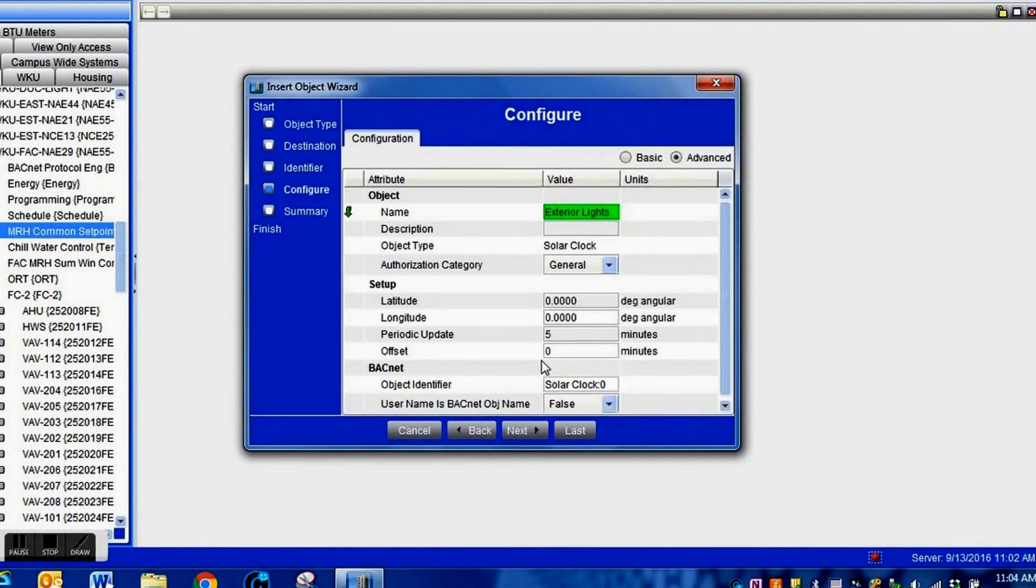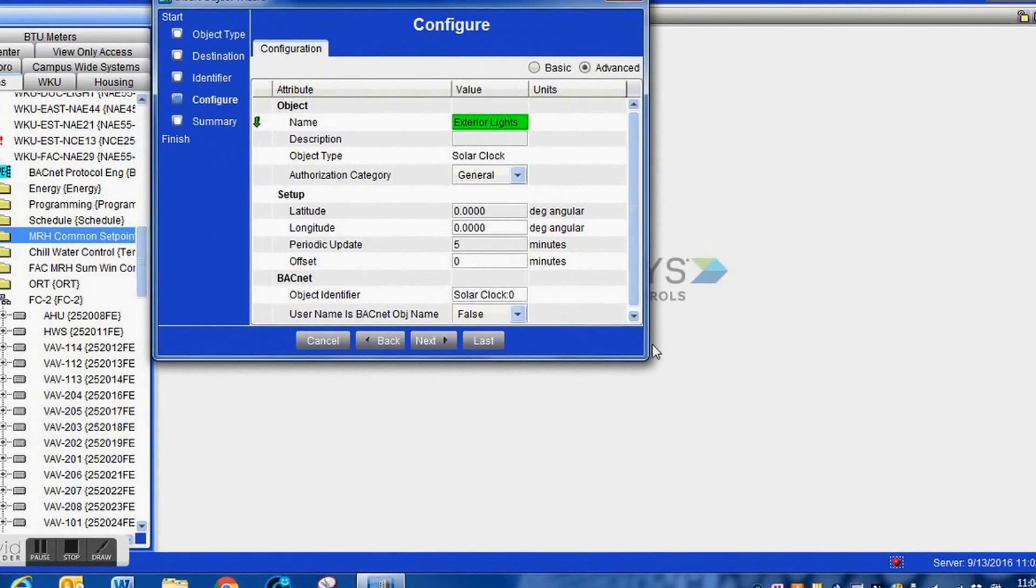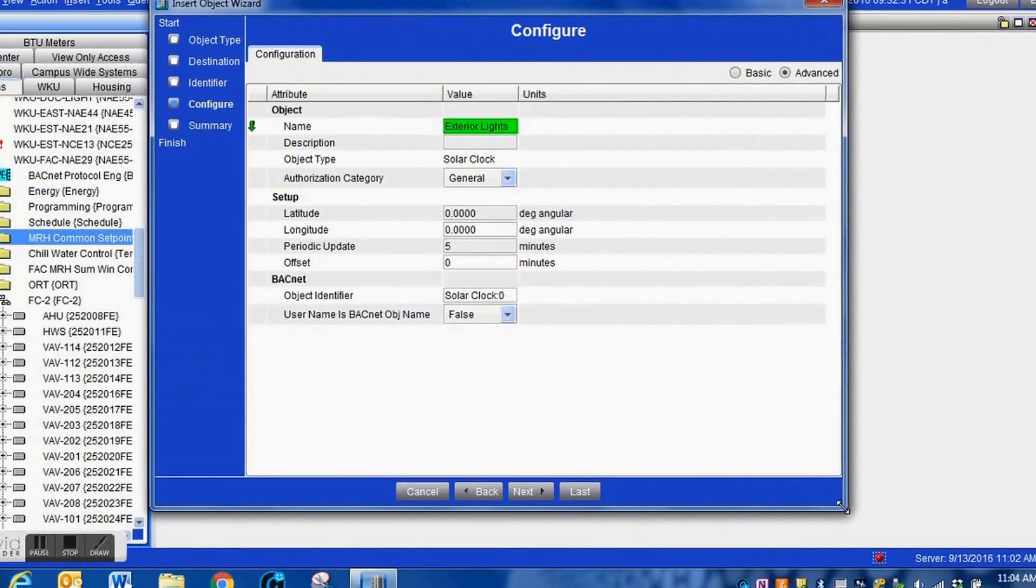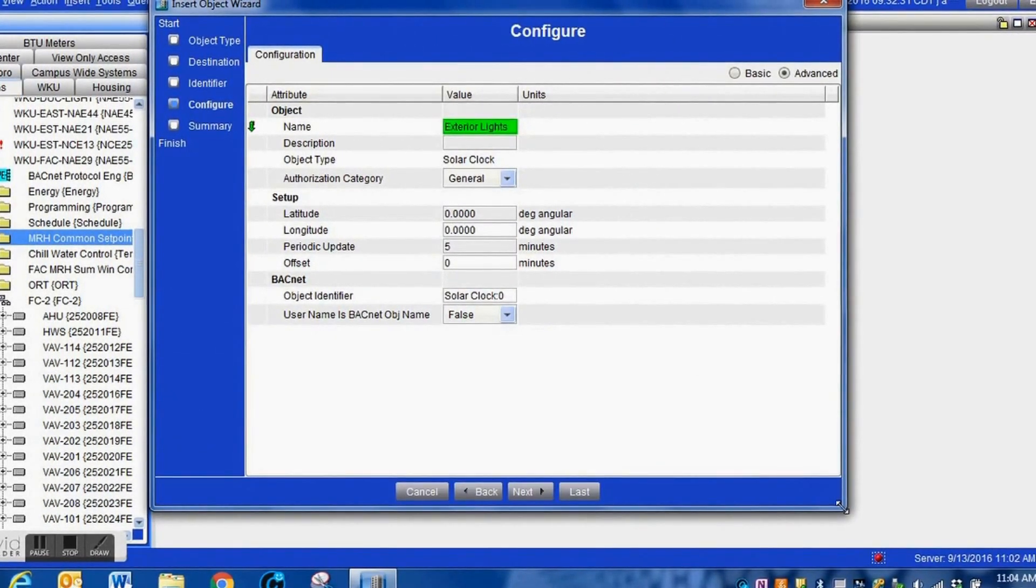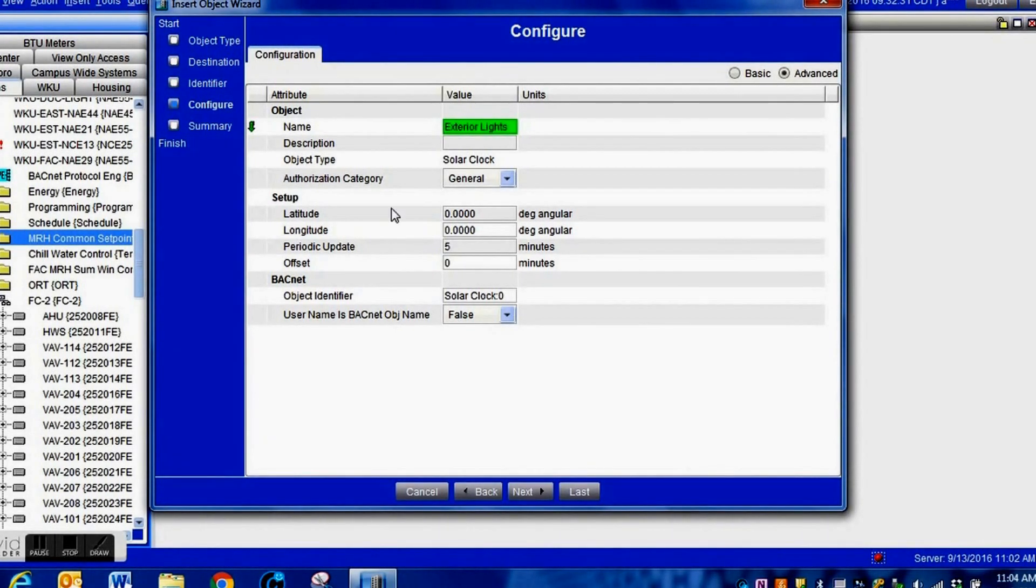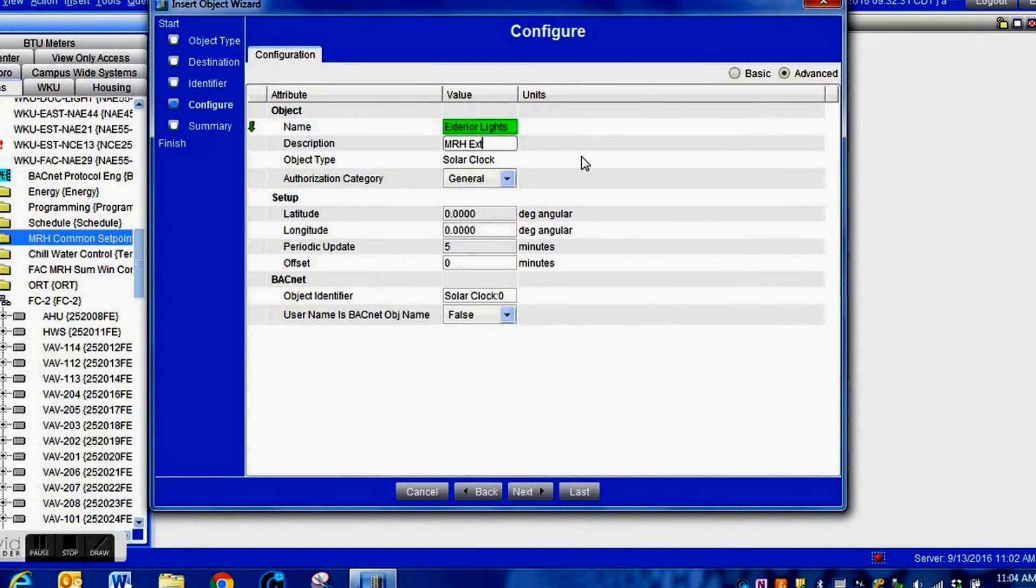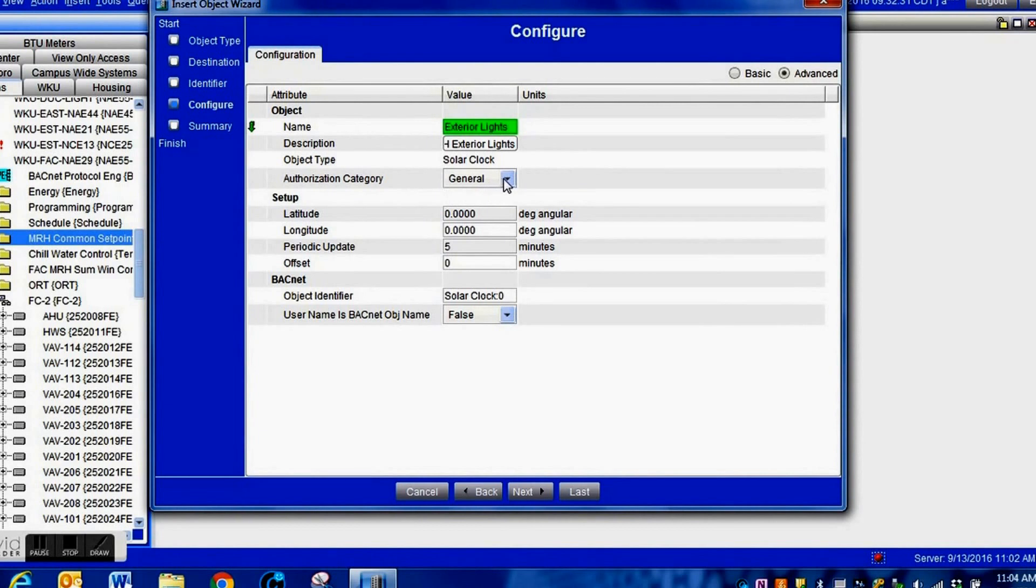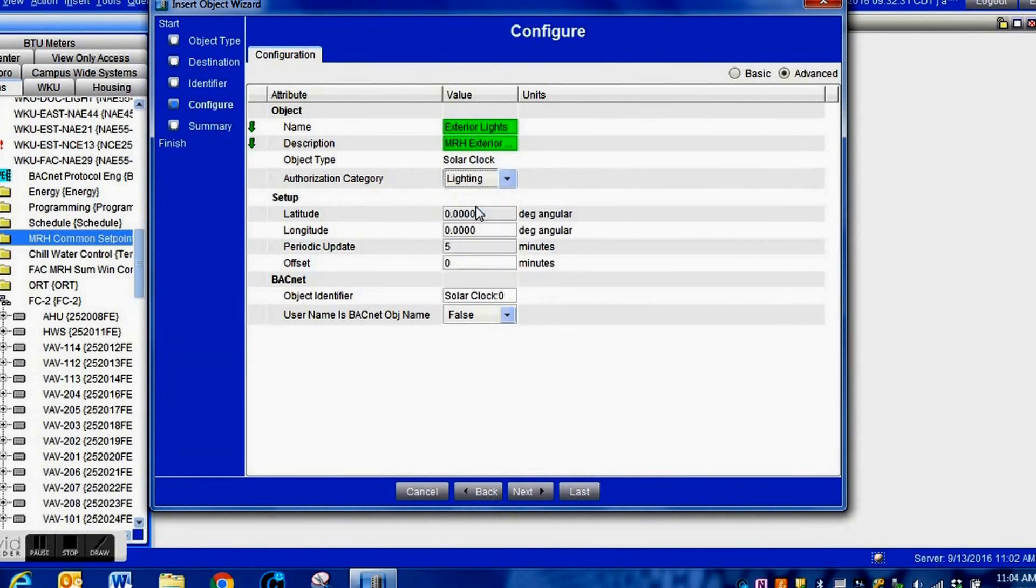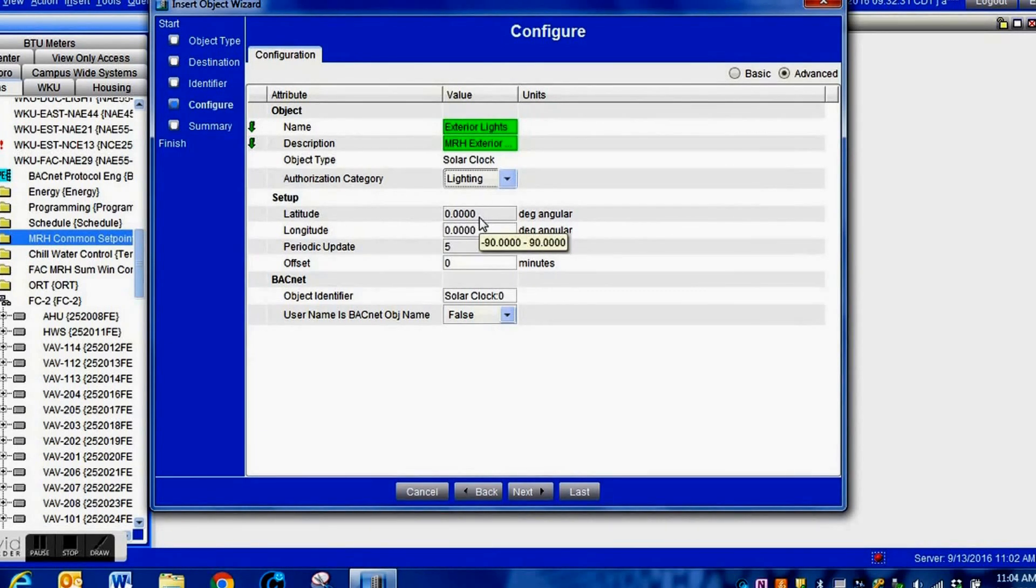This is the configure screen where you can customize a few options in the solar clock. You can delay the change from day to night, add a description. One thing you need to pay very close attention to is your latitude and longitude. You can get the latitude and longitude from Google for your particular location.